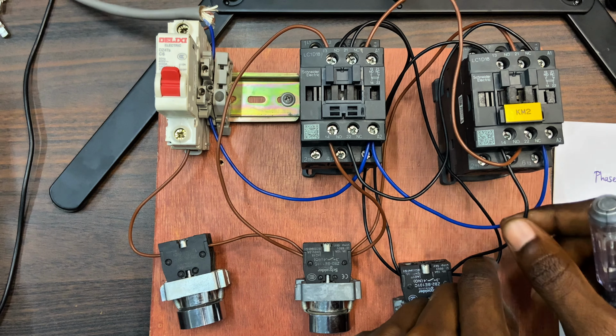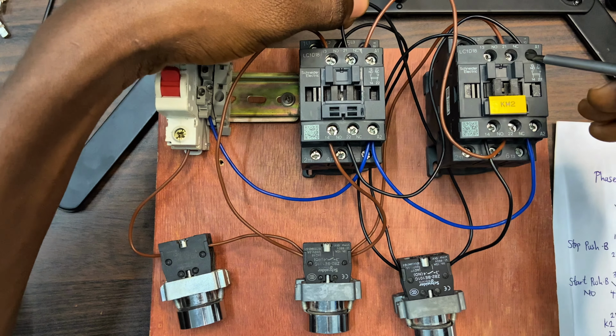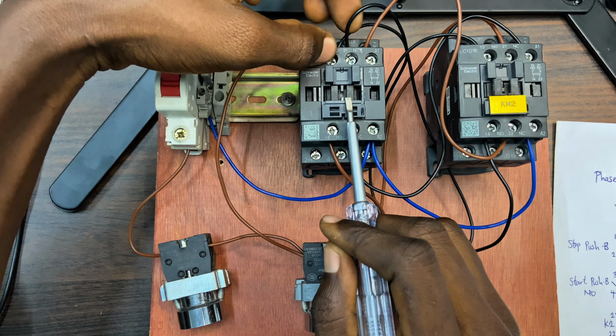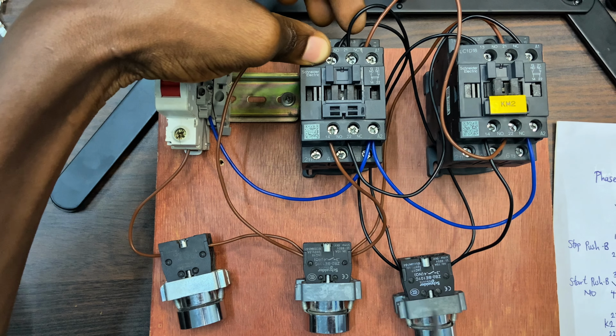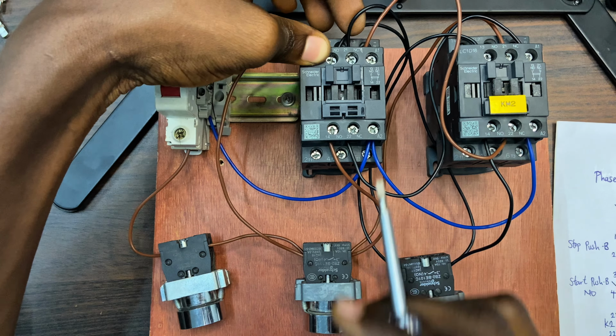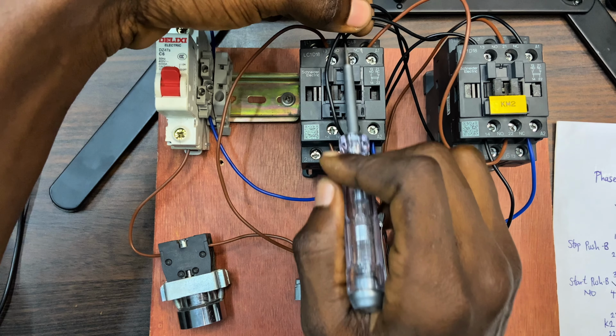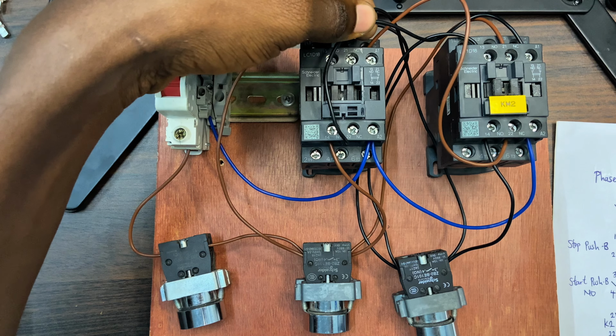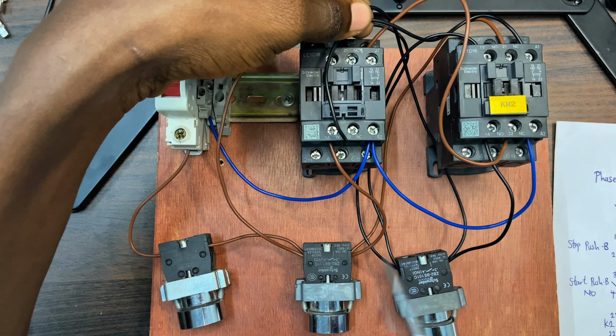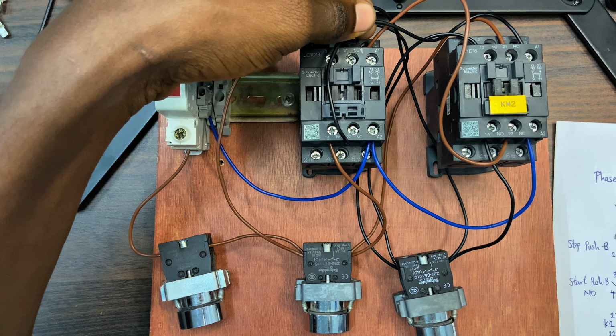And this is the switch wire to 21 and from 22 to A1 on the reverse contactor. And because this contactor has energized, right now the normally close is no more a normally close contact. Because it has energized, the normally close has turned to normally open. So this contact is now serving as normally open contact. But technically it is normally closed. But because the contactor has energized, it is serving as normally open contact. And that is why there is no flow of current from 21 to 22 and from 22 to A1. And that is the main reason why when I push this reverse contactor push button, the contactor is unable to energize.